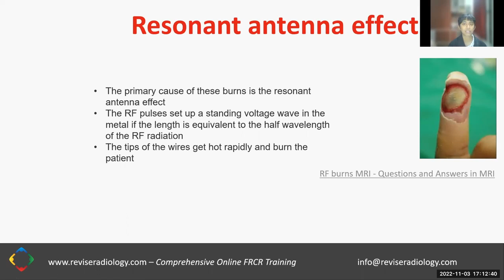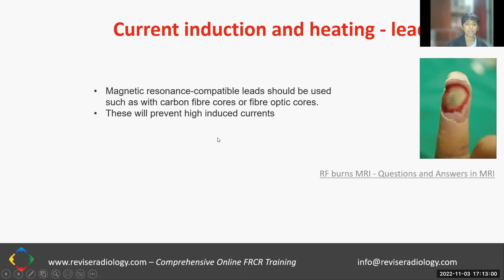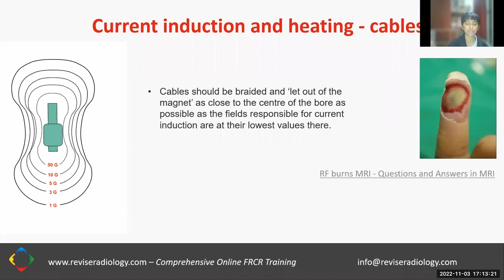So how do we prevent this from happening? Magnetic resonance compatible leads should be used, such as those with carbon fiber cores or fiber optic cores. These will prevent high induced currents from forming within the leads. Electrocardiogram electrodes should be placed as close together as possible to minimize the area of the conductive loop formed and the current which might be induced. Cables should be braided and let out of the magnet as close to the center of the bore as possible, as the fields responsible for current induction are at their lowest values there.